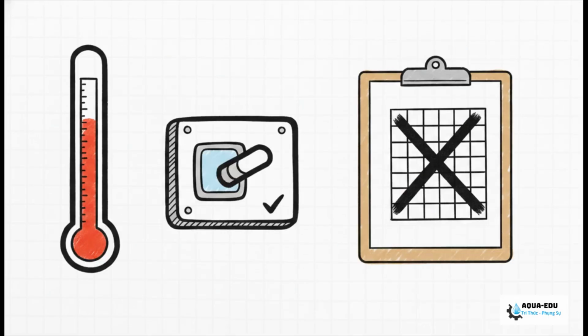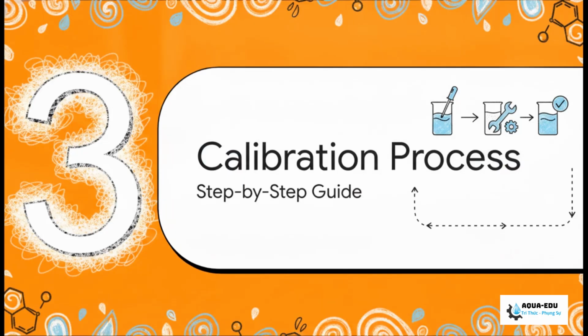You know, the environment is a huge factor here, brothers. ORP readings are incredibly temperature dependent. You absolutely must record your standard solution's temperature. If your transmitter happens to use a Pt100 or Pt1000 temperature sensor, make sure you go into the menu and turn on automatic temperature compensation, or ATC. If you don't have ATC, well, you're going to have to manually look up your target millivolt value based on the actual room temperature.